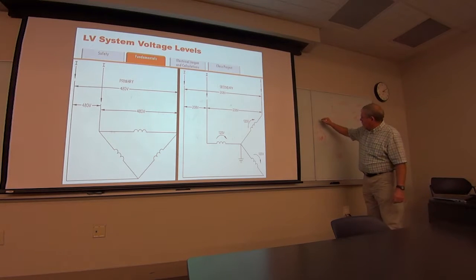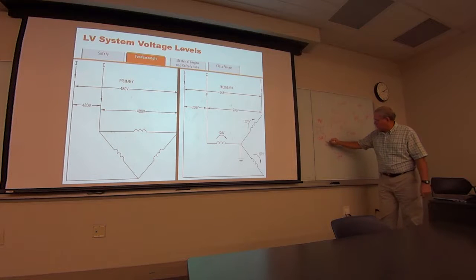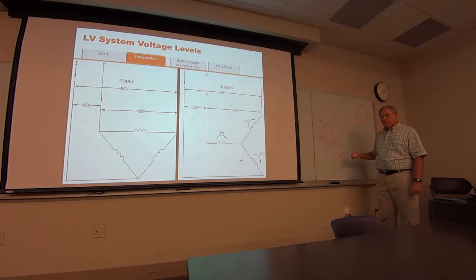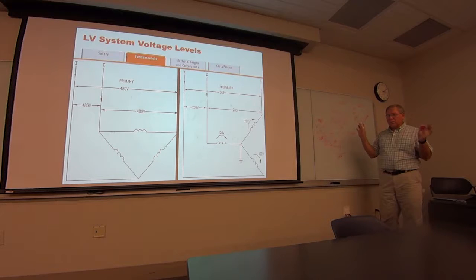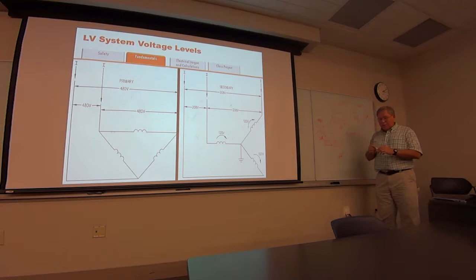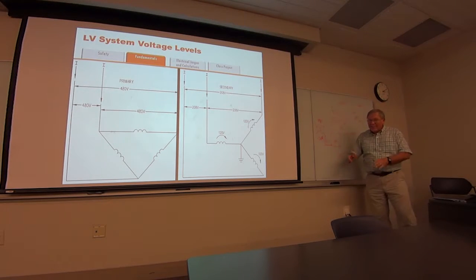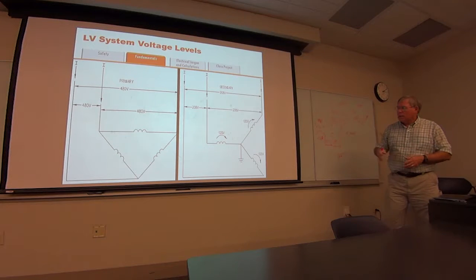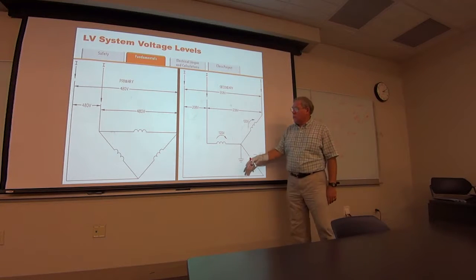And if you bought, let's say, a 480 like this, and it was 208, you could actually hook it up and make a transformer like this, where this is 480 and this is 208. You get 208 three-phase. But code requires you to ground one of these legs right here, because if you don't, there's all kinds of problems created. I'd love to talk to you about it, but it gets into a lot of details, high resistance grounding and all that other stuff. So does that answer your question? Okay. So the 208 is for the three-phase.